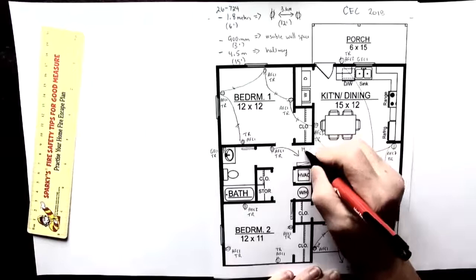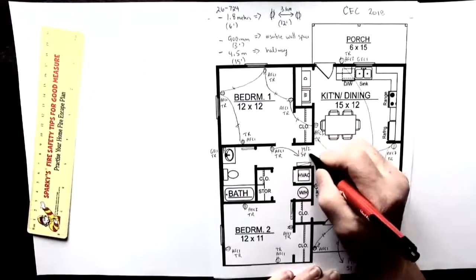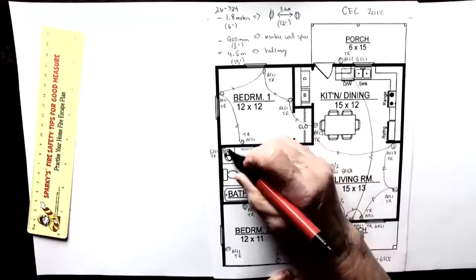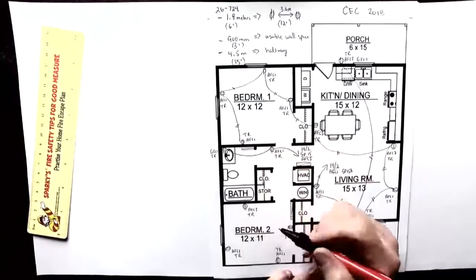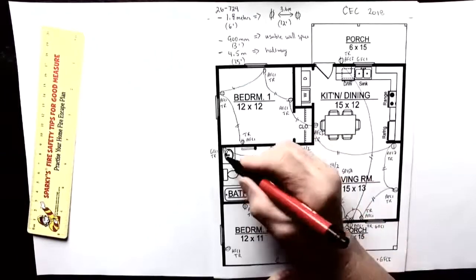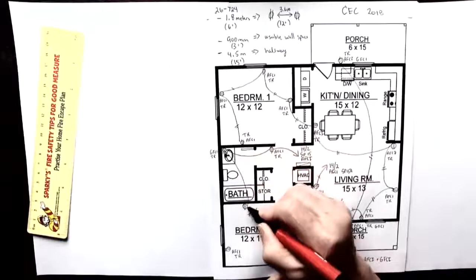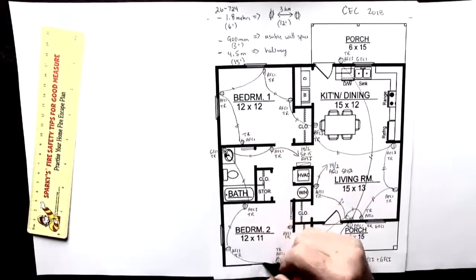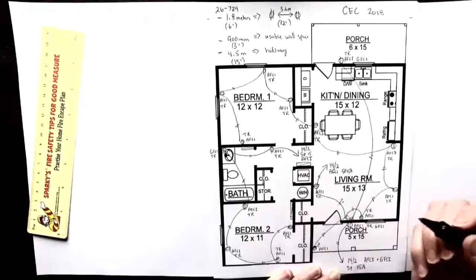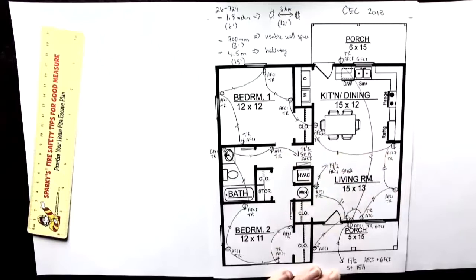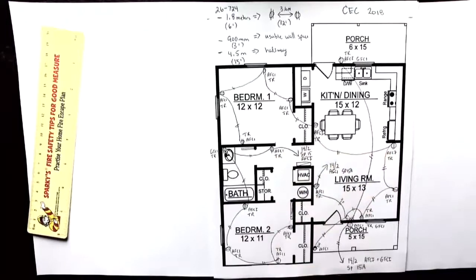This is going to be a home run. It's going to be a 14-2, single pole, 15 amp AFCI. And that'll be the first one. So that's one. We'll put a GFCI receptacle in that sink receptacle. So then it would be covered by AFCI and GFCI. And then we can come off the line side of that to pick up this. So this is just AFCI. These are 14 twos and wire around this bedroom. And I'm going to count. So 1, 2, 3, 4, 5, 6. There's no problem having six. You can have up to a maximum of 12. You don't have to load it to 12. And that would be your receptacles all wired up.